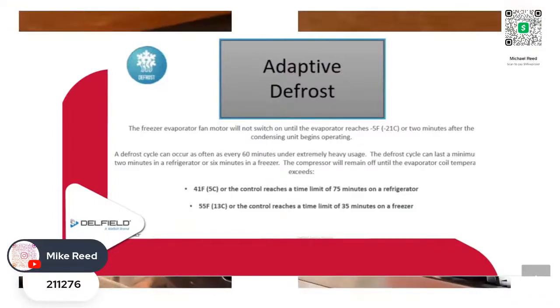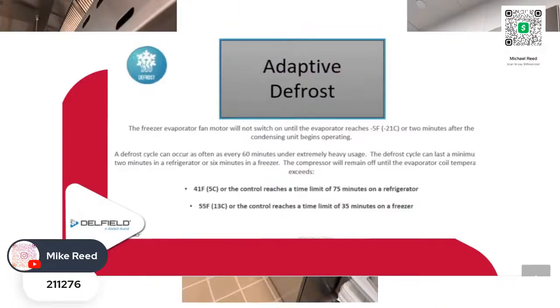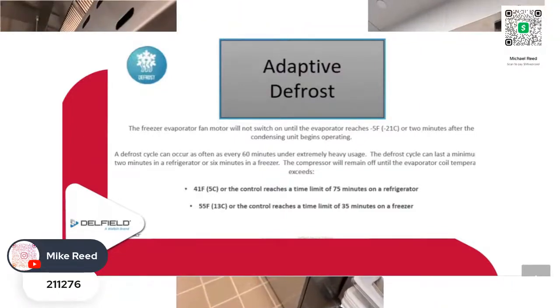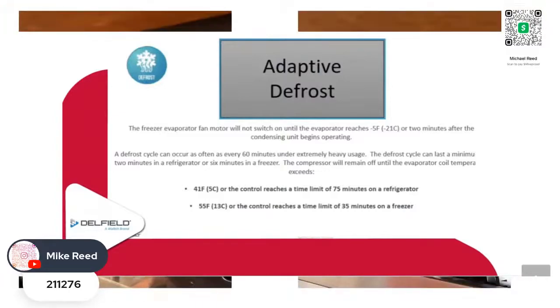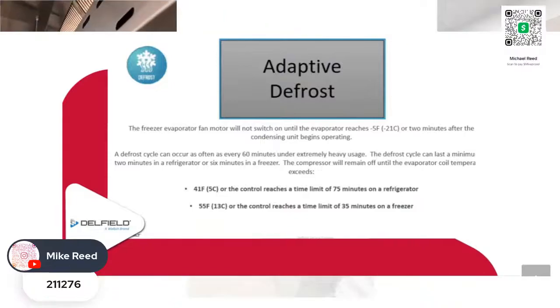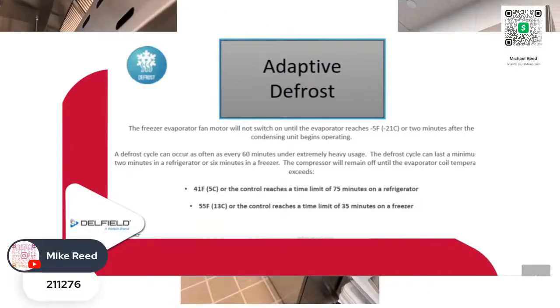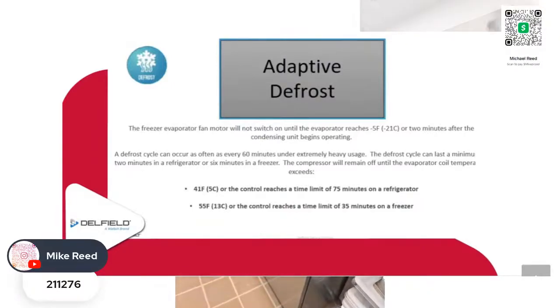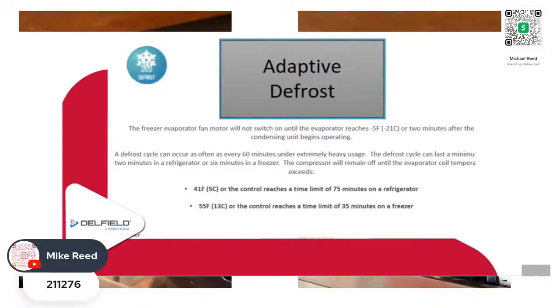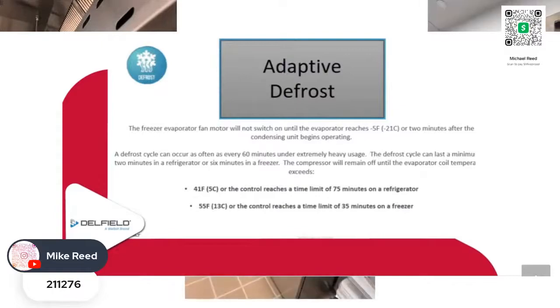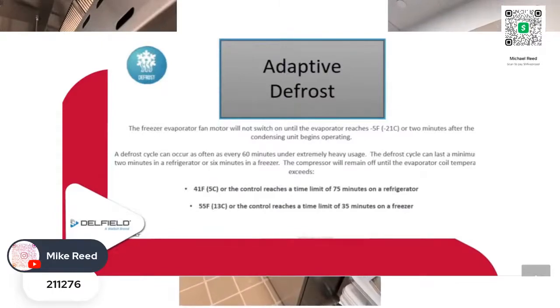The evaporator fan motor for a freezer will not run during defrost time. After the evaporator reaches -5 degrees or 2 minutes of actual time, it starts working again after defrost. So the condensing unit kicks in, and your fan delay is set at either 2 minutes or a -5 degree coil temperature.